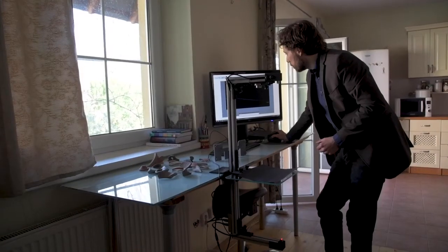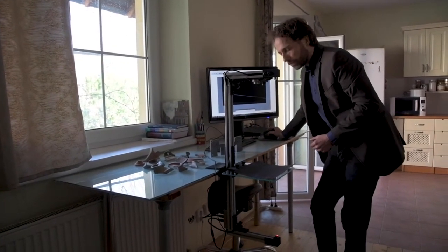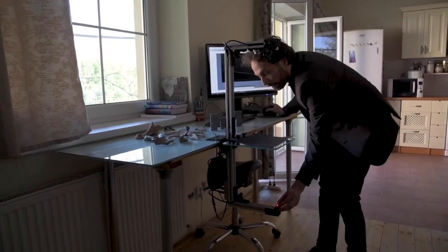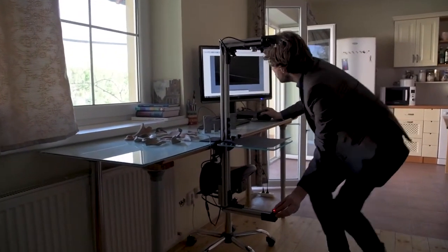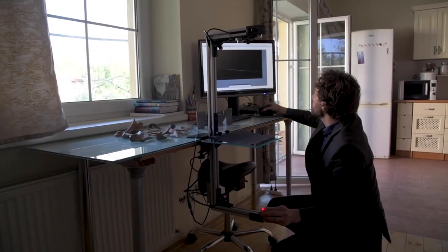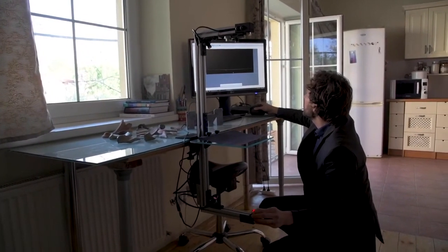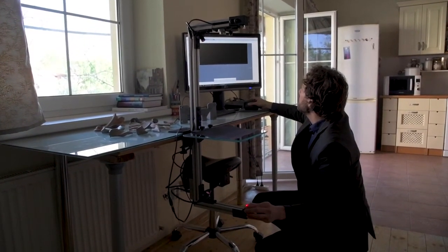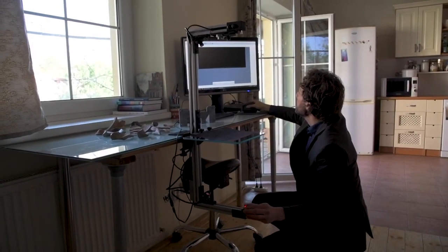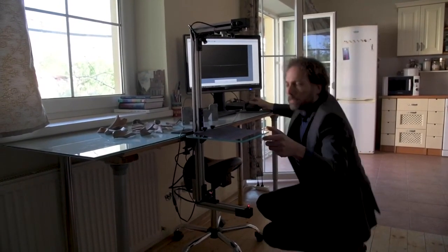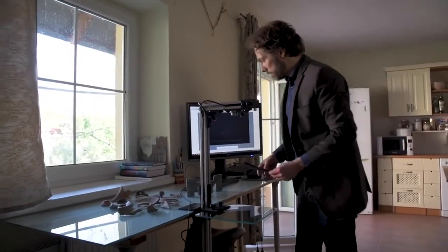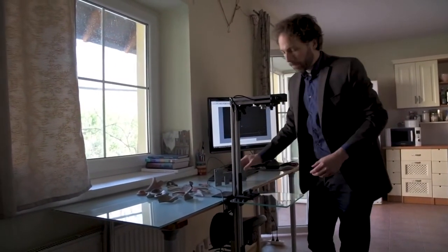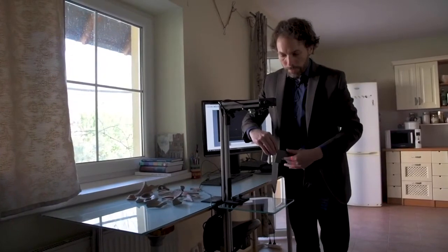So it's supposed to be like that. Now, for the lower line, the same. Again, I can adjust the exposure to see the line better. And again, I can proceed with aligning it with the camera, should be fine. And theoretically, the lines should also be aligned to each other. I can use the calibration pad to check it.